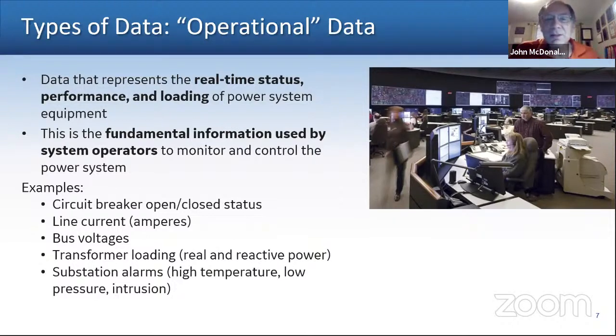The operational data is what we're very familiar with. This is the information in the field that we need to send to the control center, that operators use to monitor and control the grid. This data comes in every 2 seconds, all the time. It's a time series: voltage, current, real power flow in megawatts, reactive power flow in megavars, the open and closed status of a circuit breaker or switch, current in amps, voltage around the system, loading on the transformer (both real and reactive power), and alarm information. Important information, and this is what we're used to.